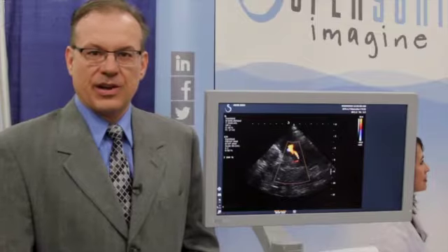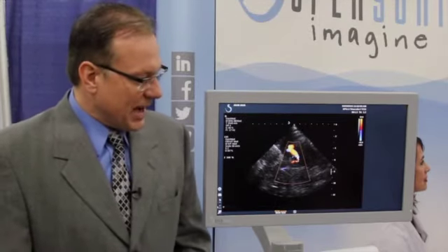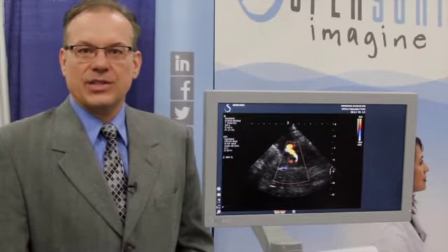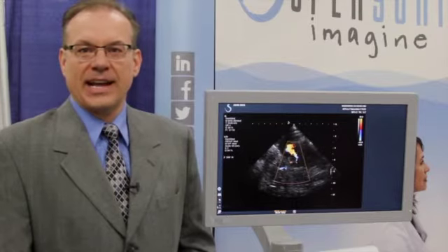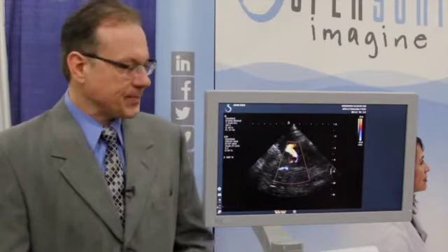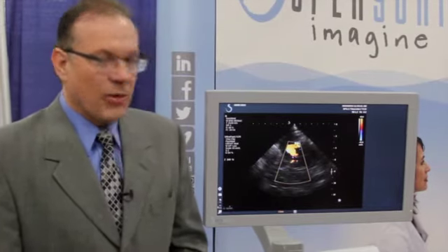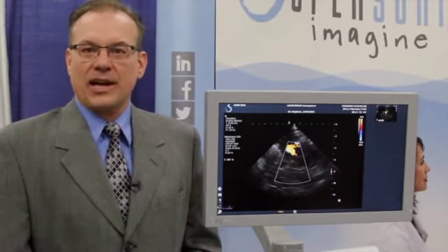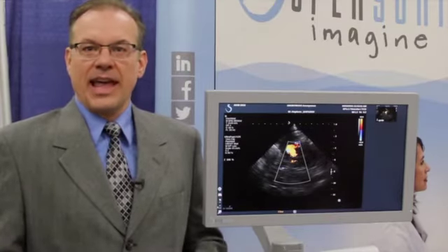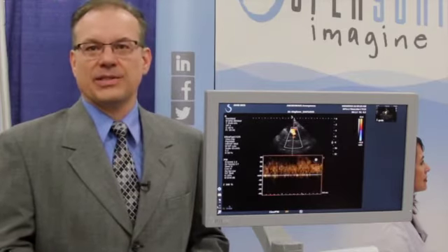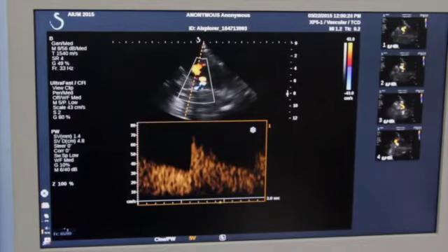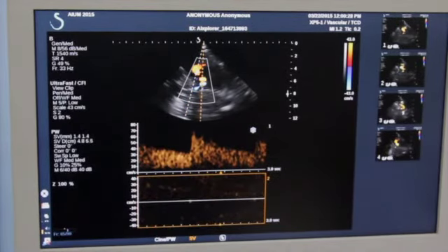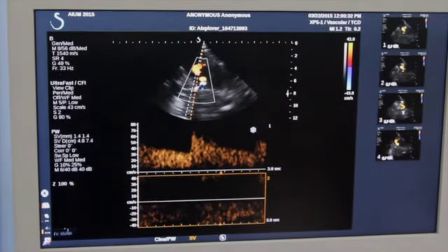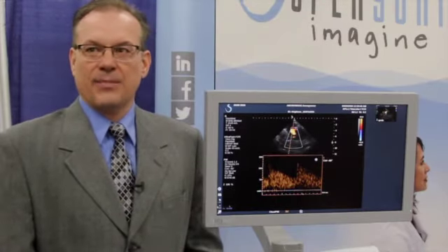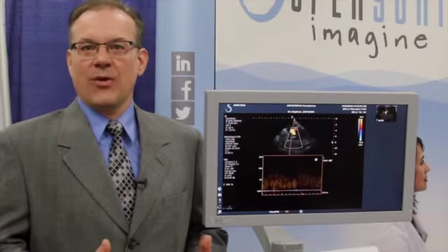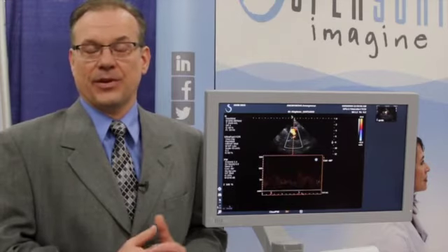So Erin is going to apply the transducer for transcranial imaging here. She's going to optimize the image and simply press one button, which is called Acquire Ultra-Fast Doppler, to capture up to 4 seconds of velocity information in that entire 2D area. Now, once the acquisition is over, just a few seconds, she can now post-process the data. She can apply gain correction, scale correction, and of course what's really interesting is to be able to position multiple pulse wave Doppler sample volumes into the image. Now you can take a look at the flow velocity information from multiple segments of the MCA, even the ACA at the same time. She can adjust the baseline and scale, she can tune it up a little bit, and present one image to the radiologist for reading rather than having to synthesize information from multiple PW Doppler sequences.